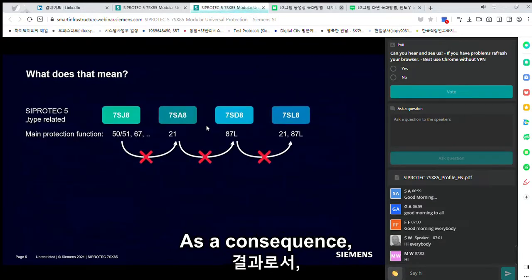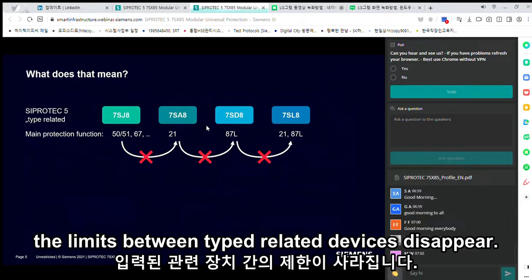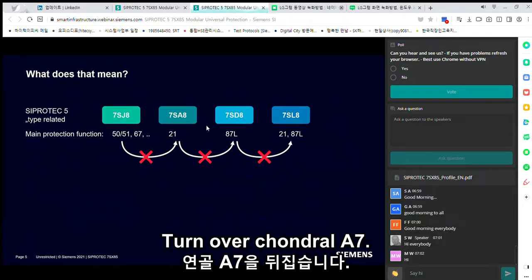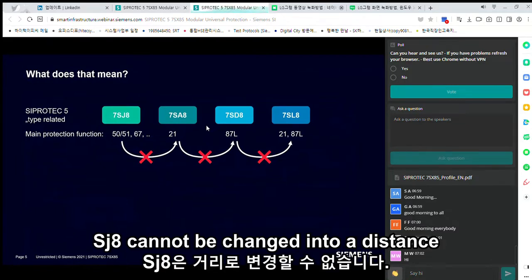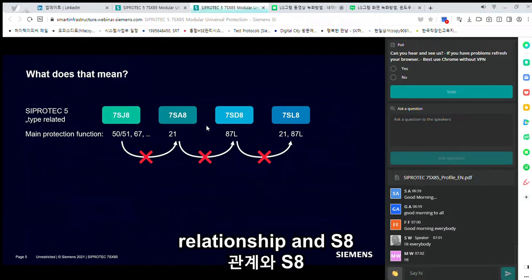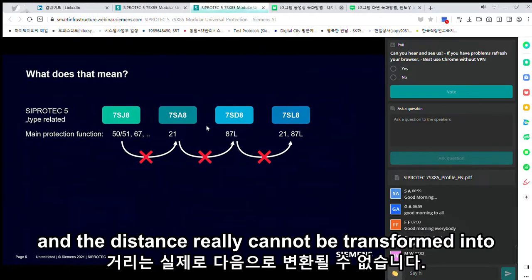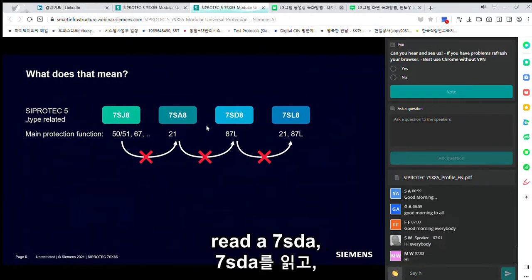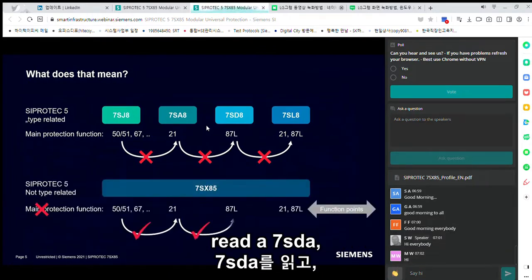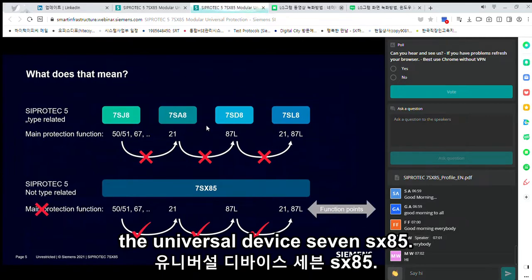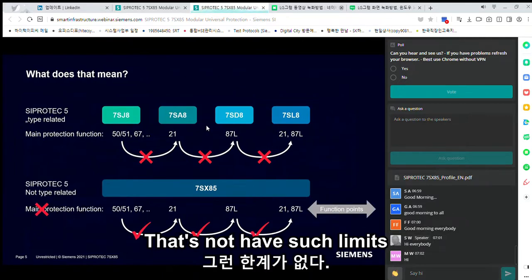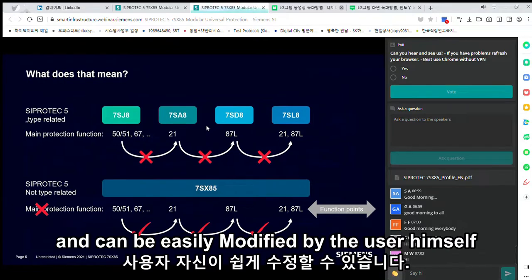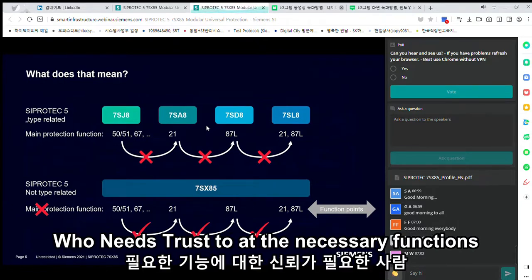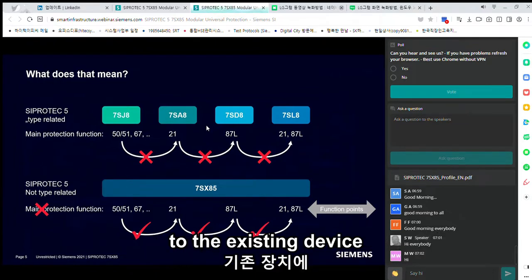As a consequence, the limits between type-related devices disappear. Where an overcurrent relay 7SJ8 cannot be changed into a distance relay 7SA8, and a distance relay cannot be transformed into a line differential relay 7SD8, the universal device 7SX85 does not have such limits and can be easily modified by the user, who just needs to add the necessary functions to the existing device configuration.